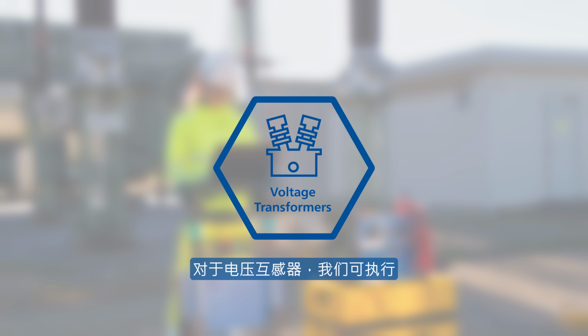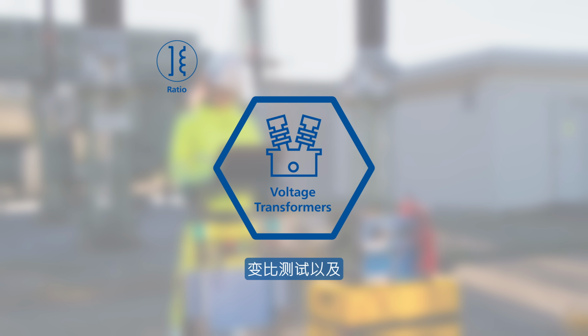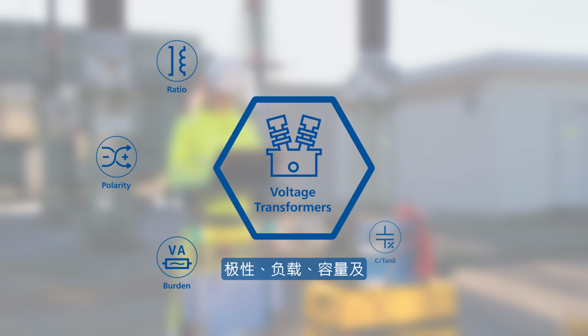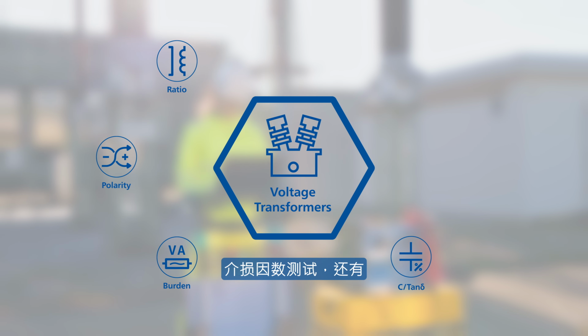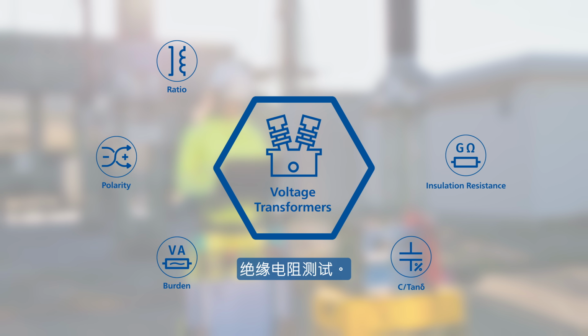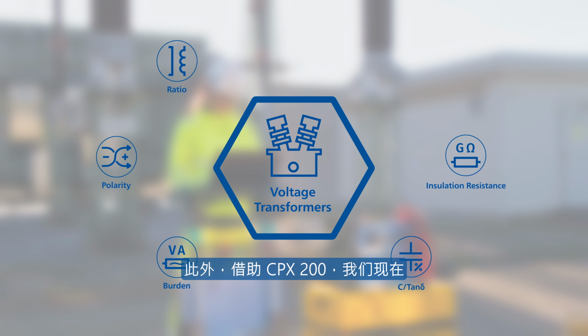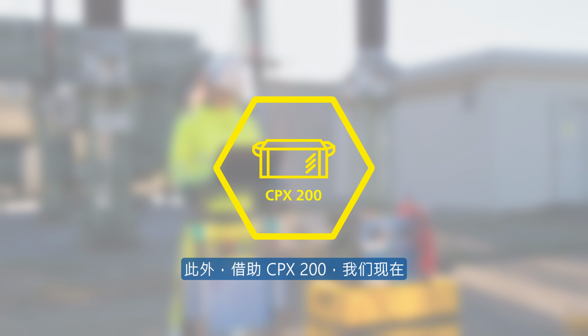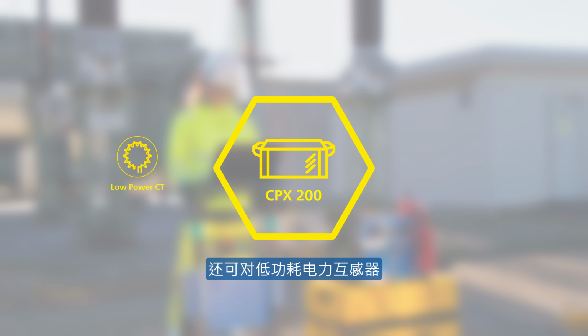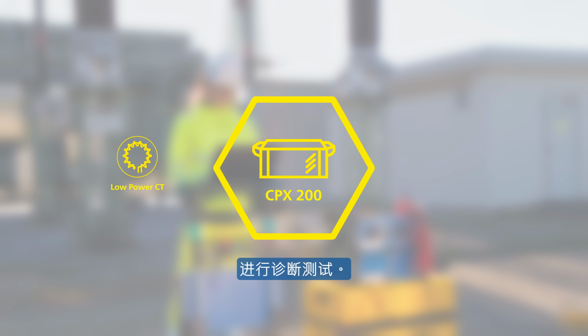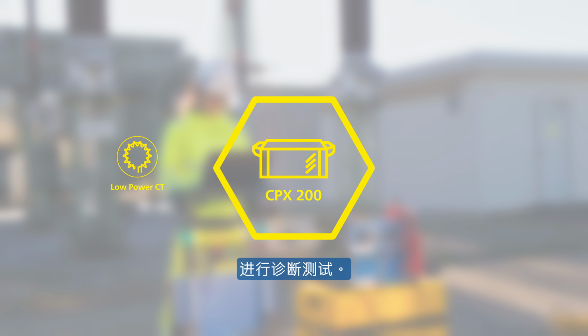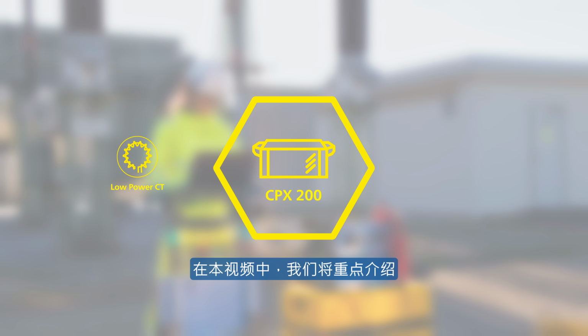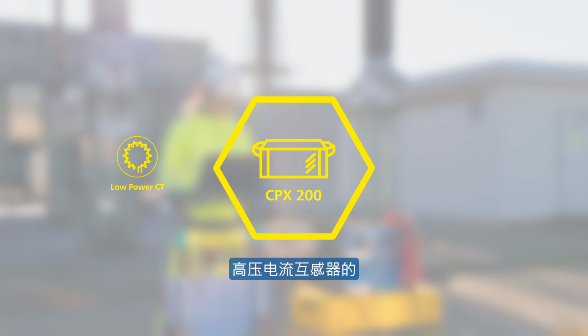On voltage transformers, we can perform ratio tests as well as polarity, burden, capacity, and dissipation factor tests, and also insulation resistance tests. Additionally, with the CPX200, we can now also perform diagnostic tests on low-power instrument transformers, the so-called LPITs. In this video, we'll focus on standard electrical tests for high-voltage current transformers.